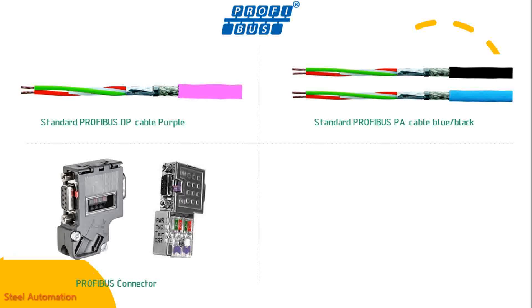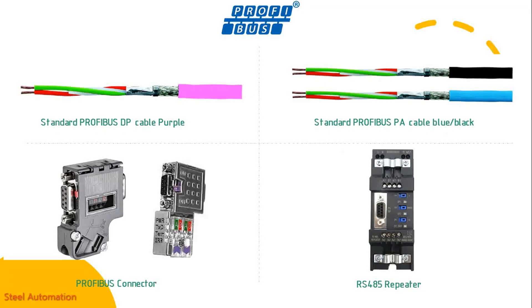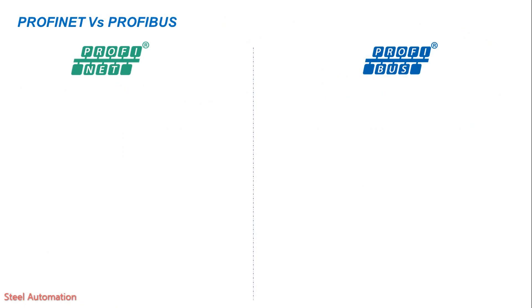A Profibus connector is used to terminate the cable. The RS-485 repeater connects two Profibus bus segments in RS-485 technology with up to 32 devices. It provides transmission rates from 9.6 kbps to 12 Mbps. It is used when more than 32 stations are connected to the bus or the maximum cable length of a segment is exceeded. These components will be discussed in detail in other videos.